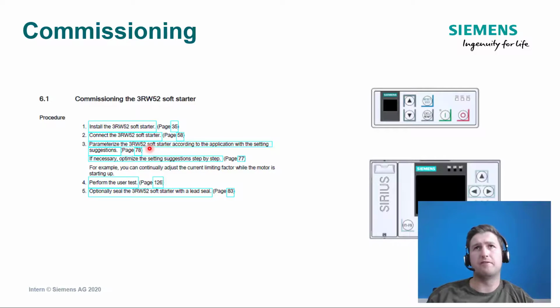So you do have to be careful with that as well, because if you set the current limitation function too low and the ramp up time has elapsed and you haven't actually reached full speed of the motor by the time it reaches that ramp up time, it'll enter bypass mode and the device will go into fault and it won't initiate the start. And once you've done that, you can perform a test by starting and stopping the motor, just to ensure that the device is operating correctly, and then you can use a seal if you wish to.